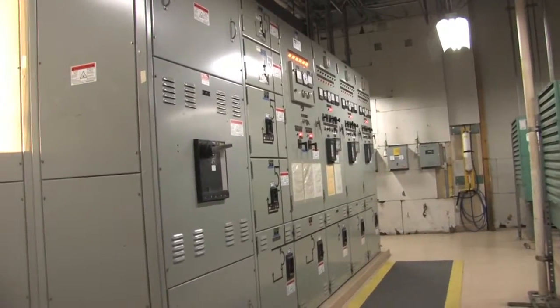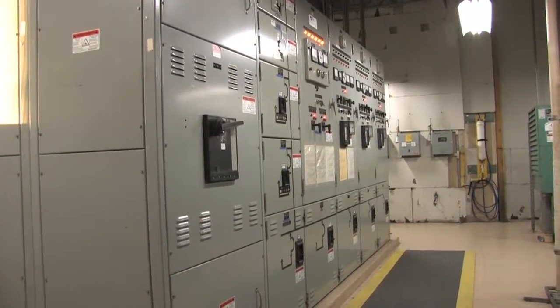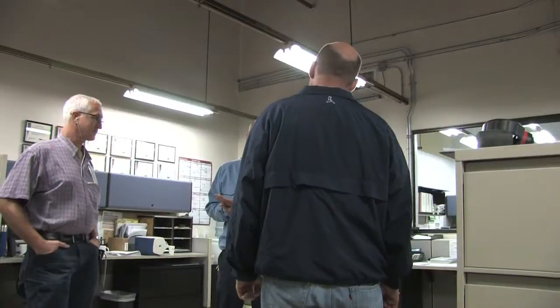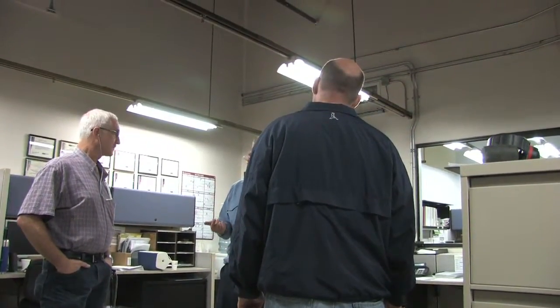They had a history over the last 15 years of where those two substation transformers were 10 years ago, where they were 5 years ago, and where they are today. And you saw the deterioration from the last shutdown, where they tested fine. So the bank hires us to come in every 5 years, and we come in and do a complete shutdown. Now, it sounds like we just go in one weekend and do it.